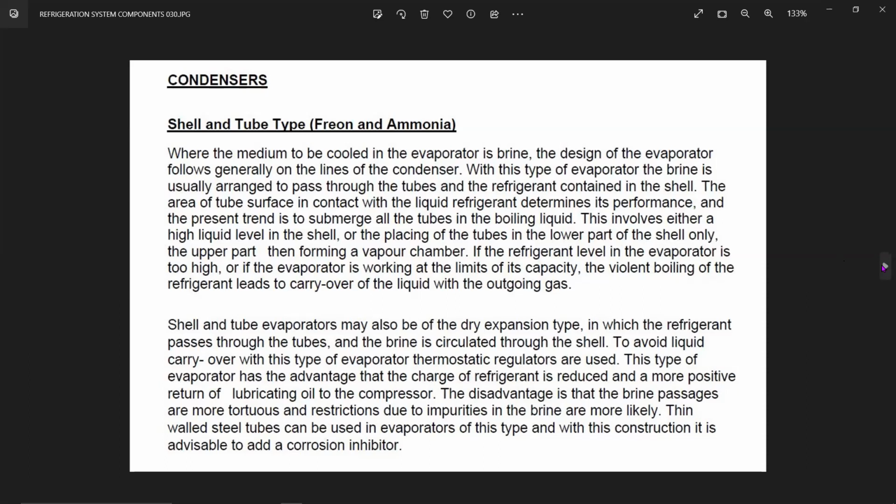To explain the situation, one of my vessels, a reefer vessel, had about 12 holds. Not that big, but 12 different holds, like four levels, three levels in each hood, and four of them. All of them had these brine coils. The problem with the brine coil is that when the vessel gets old, it starts leaking.